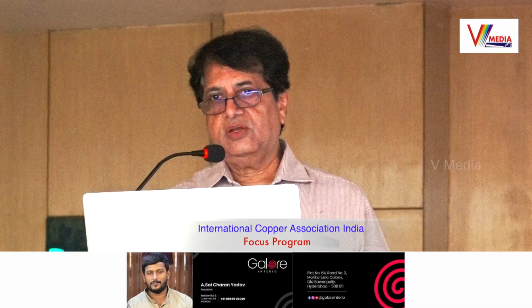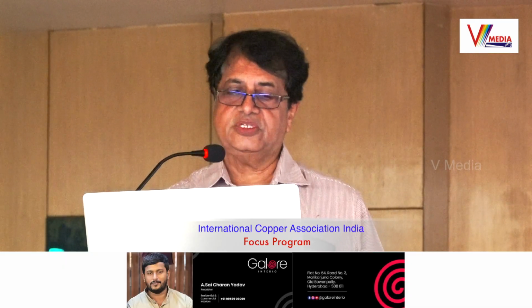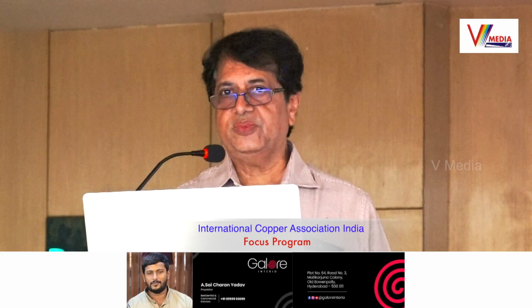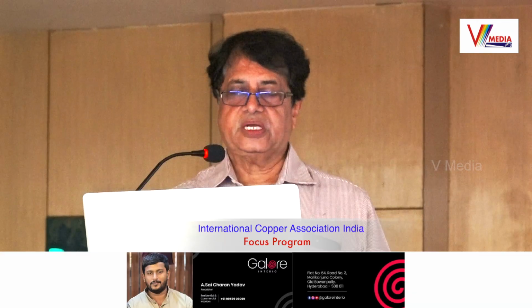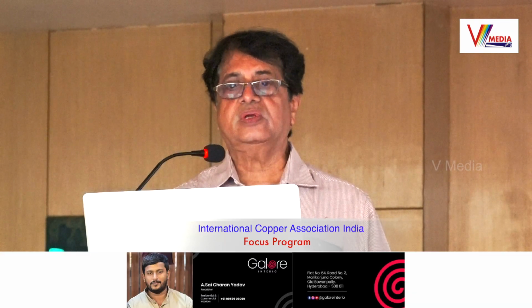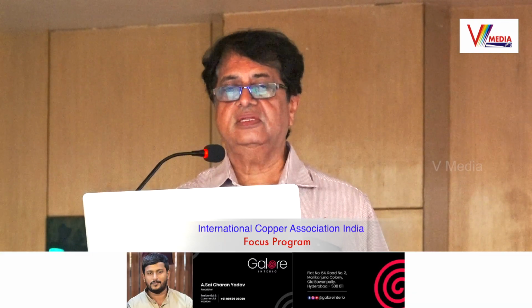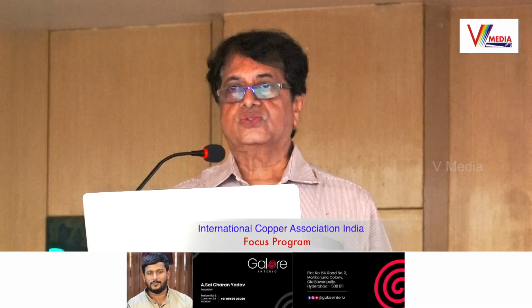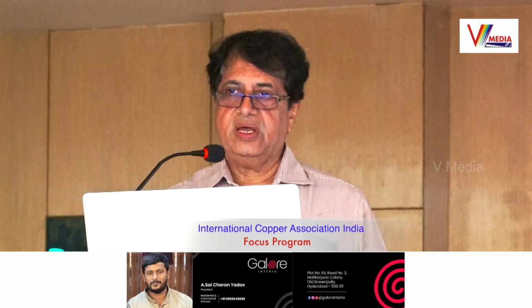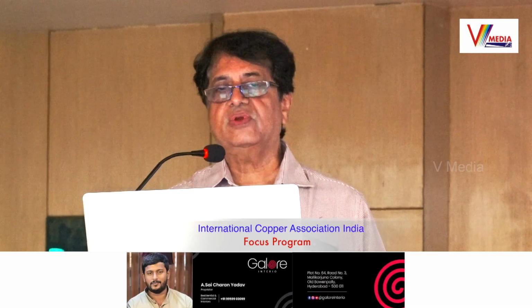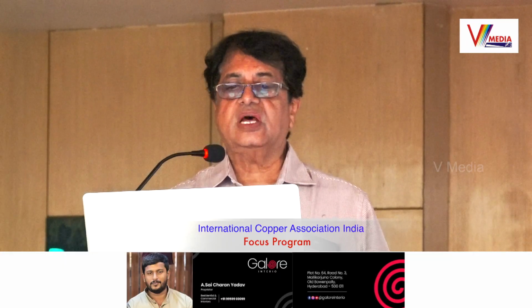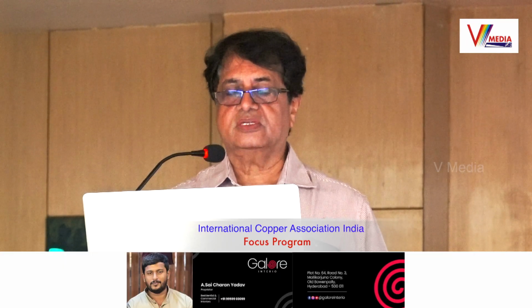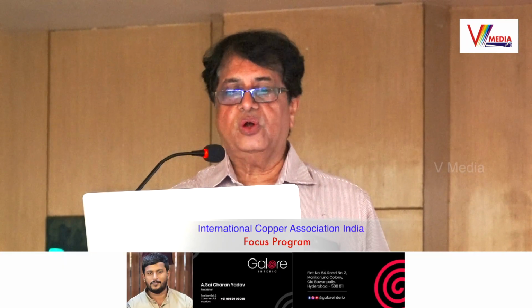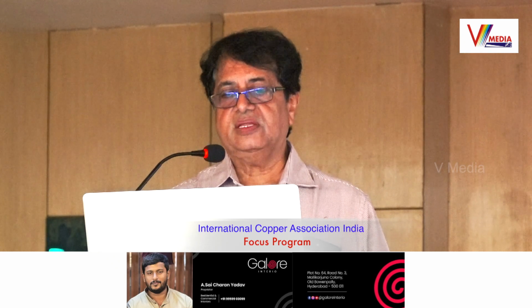Central Electricity Authority regulation number 65 tells us that you have to take proper permission from the electrical inspector and the owner of that line before carrying out any construction in the vicinity of that line. So some documentation is required and some clearances you need to take from these two authorities before starting your actual construction work. So this is a very important right which needs to be considered by the architect at the very beginning stage.